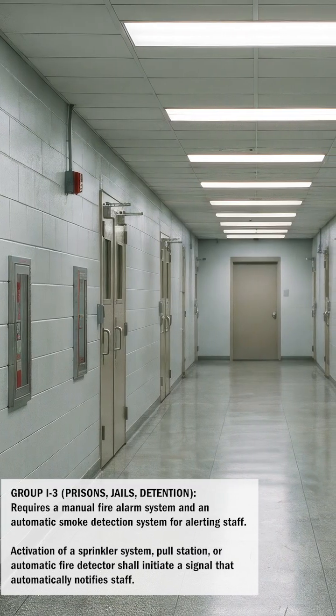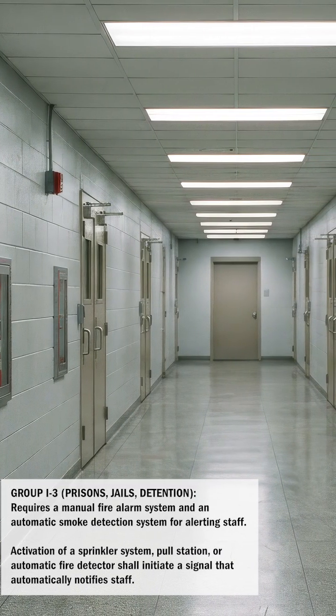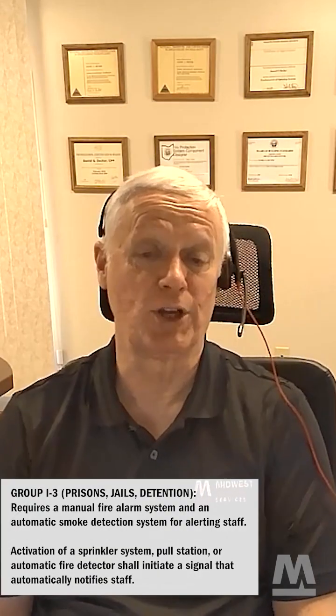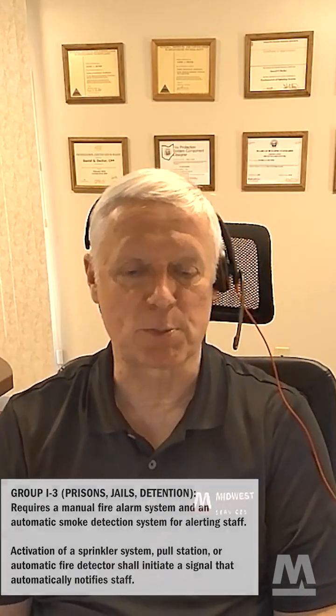Group I3, dealing with prisons, jails, and detention, requires a manual alarm system and an automatic smoke detection system for alerting staff. The activation of a sprinkler system, pull station, or automatic fire detector shall initiate a signal that automatically notifies staff. It isn't a requirement to notify occupants that are behind bars because there's not a whole lot they can do about it. The pull station placement exceptions: pull stations are not required at exits if they're provided at staff-attended locations, and pull stations in detainee areas are permitted to be locked provided staff members are present and have keys.